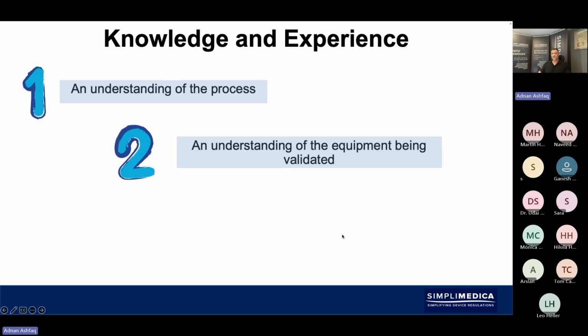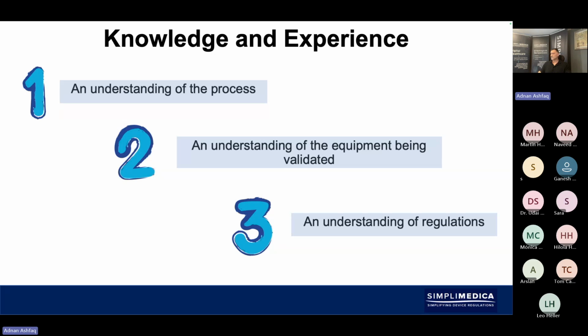Knowledge and experience, of course: understanding of the process, an understanding of the equipment being validated, and also understanding the regulations, the goalposts, what's required. We have different legislations. We've got the FDA requirements. We've got ISPE GAMP, which some of you may be familiar with, Good Automated Manufacturing Practice. We'll also be touching upon that in the time to come. And then also the specific jurisdictions may have other requirements. So it's also important to look at wherever commercialization of the devices is taking place, and that's something that the engineering team should work closely with market access on: which markets are being accessed, and do they have any specific requirements over and above the ISO, over and above the FDA guidance and the GAMP guidance. There may be some other requirements.